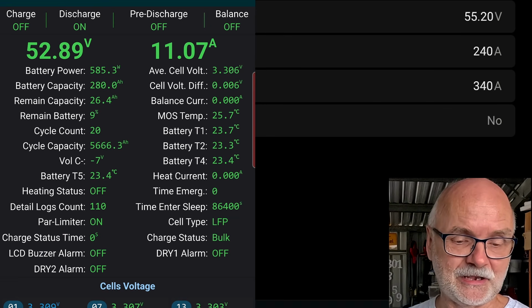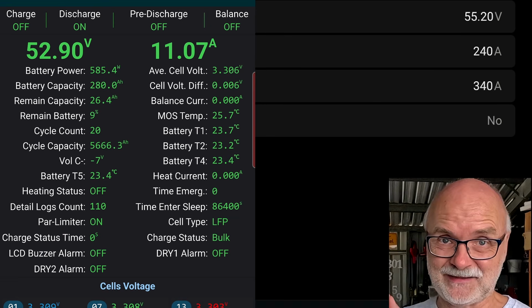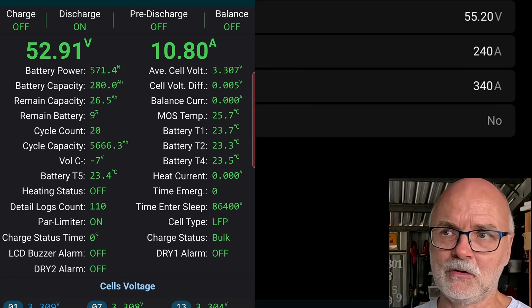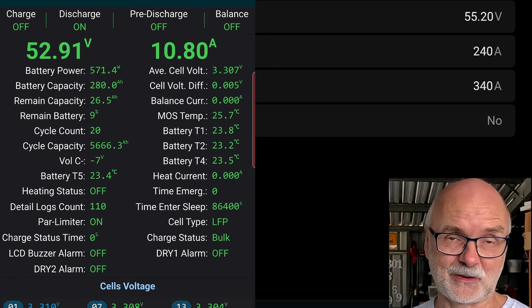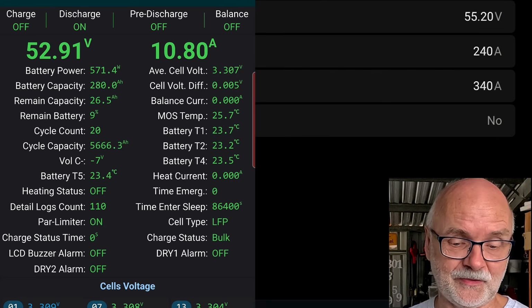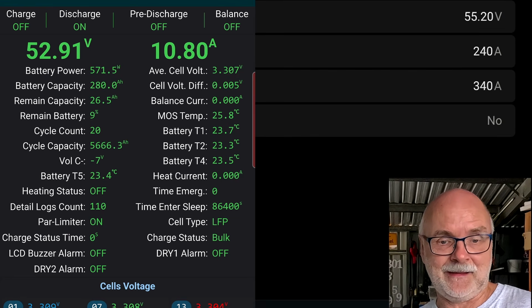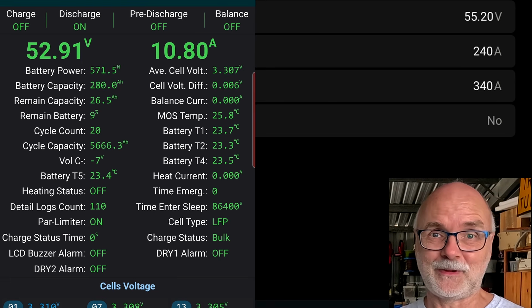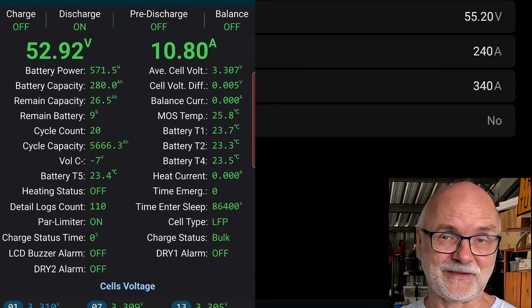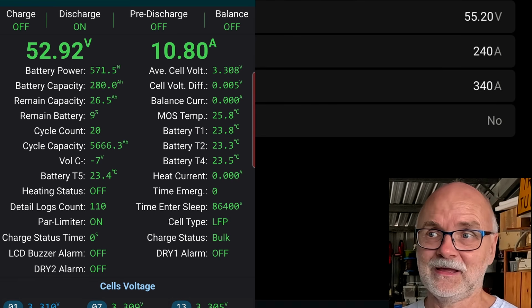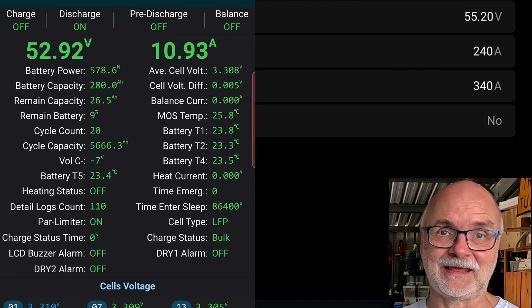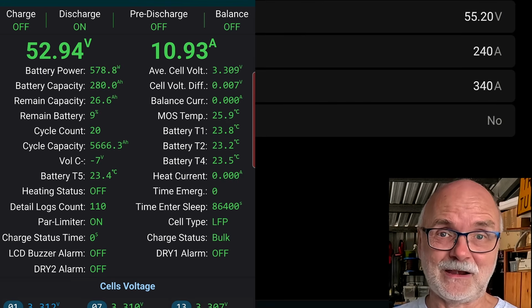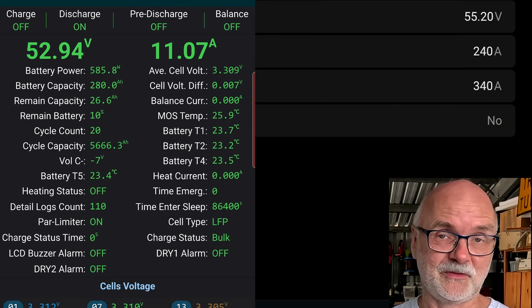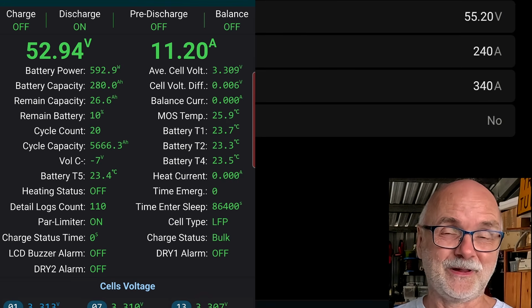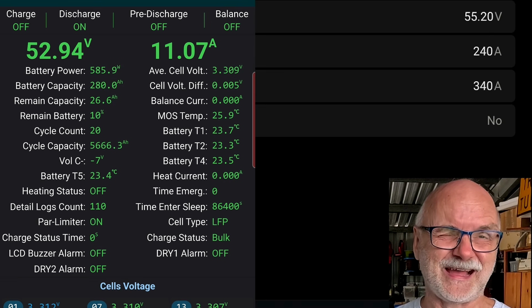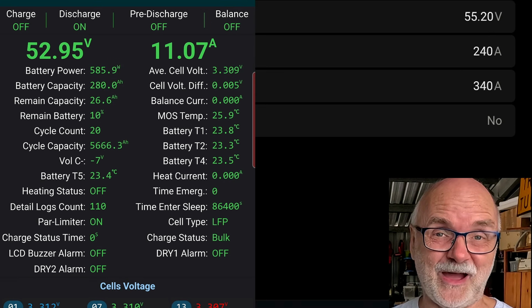So the alarm has now cleared in the BMS. Charge MOSFETs are still off. And we can still see now we have a reduced charge current limit requested from your inverter. And this battery with the overcurrent fault is still charging with 10 amps. Yeah. And you can see now the difference. We are not going back to an alarm after 3 seconds as we did without the current limiter. And we are also not increasing the CCL again to 320. So if you have the current limiter active and it actually triggers with an overcurrent protection at some stage, it will stay active until the current goes under, oh, no quote me, 5 amps, I think.